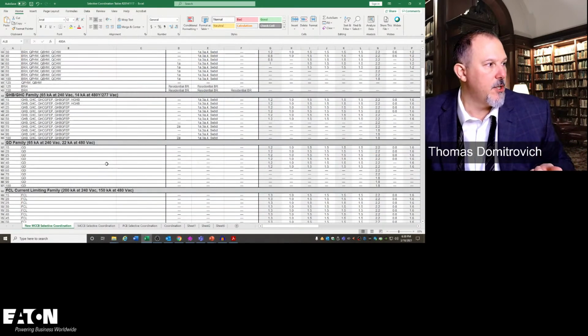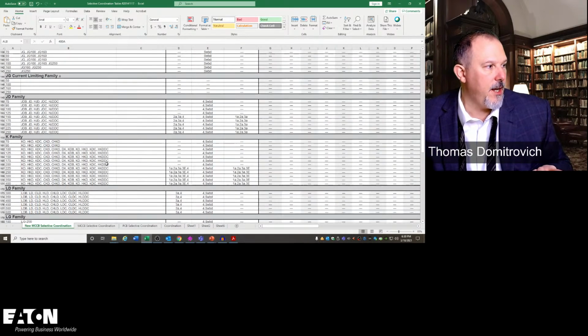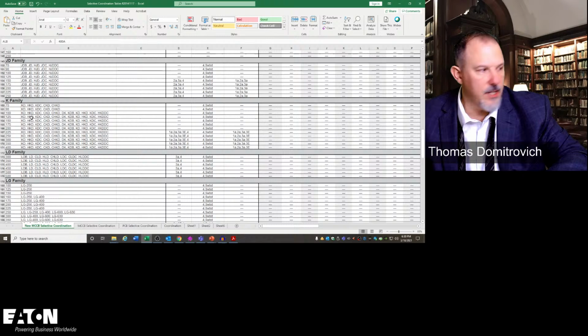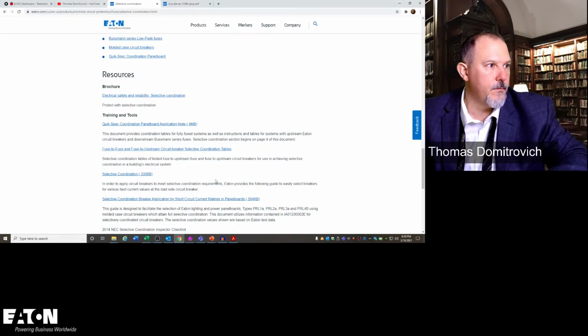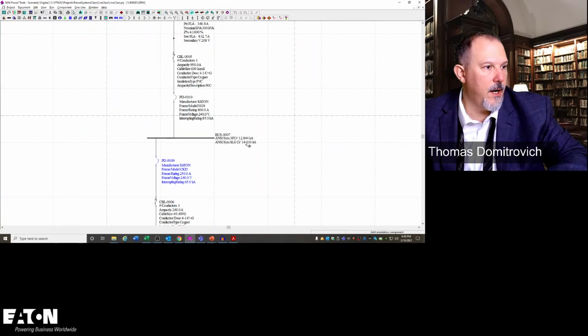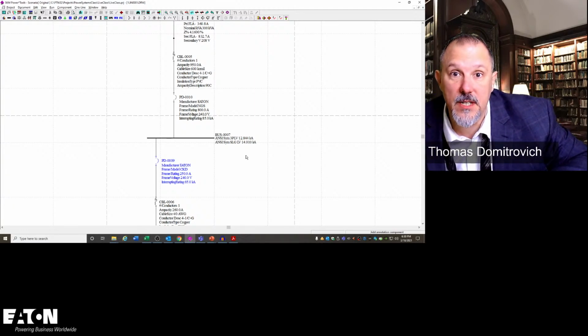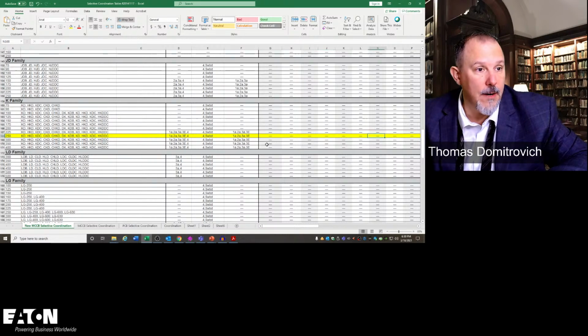I'm going to go to the left-hand side now. I'm going to scroll down to get to a CKD, the KD breakers, J, K. And that was a K-frame 250, right? So I'm going to highlight that yellow. And what's my fault current? My fault current is, I'm going to use 14,000 amps. So now I've got to scroll to the right to find something 14 or higher.